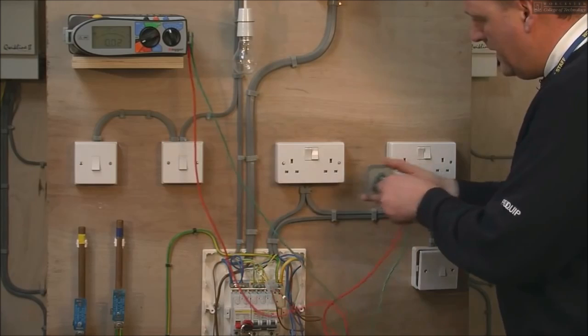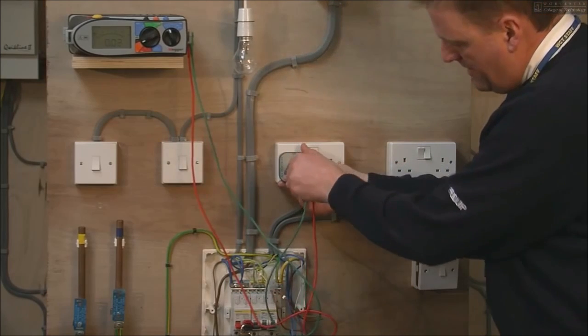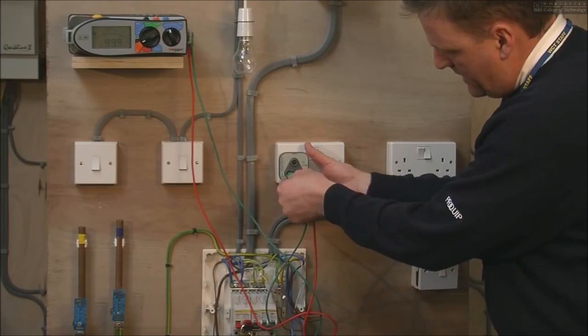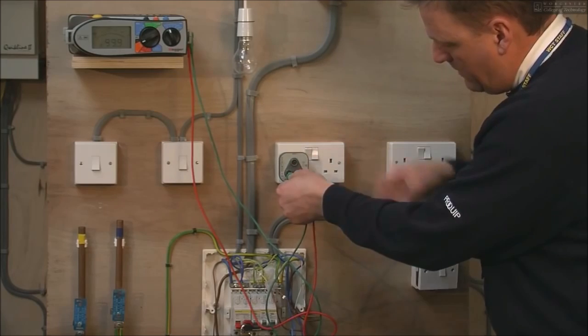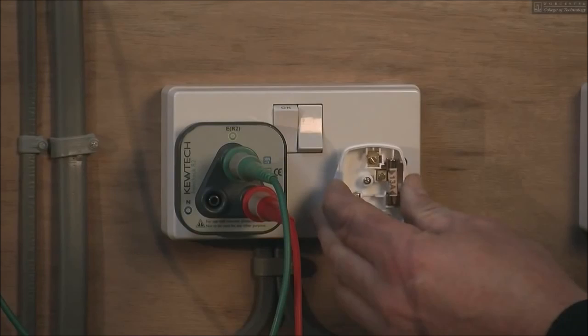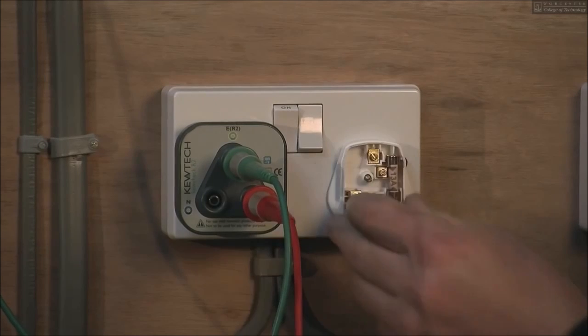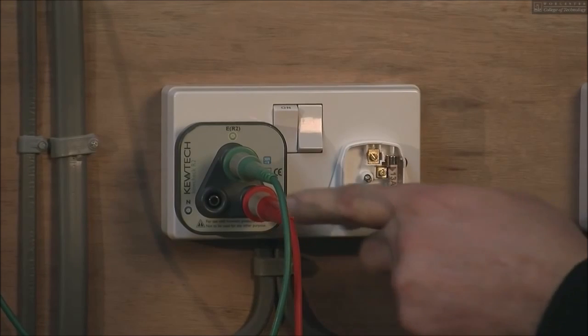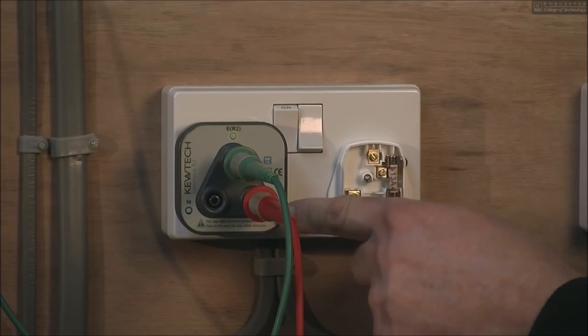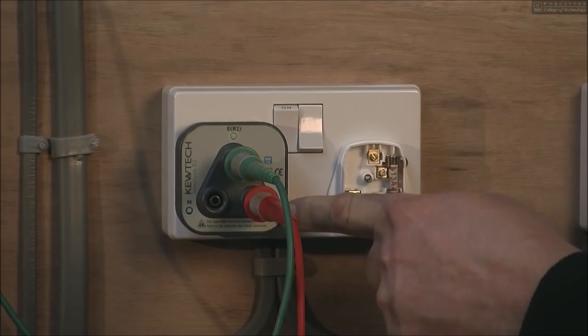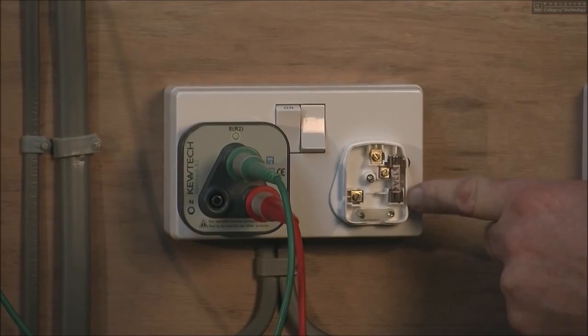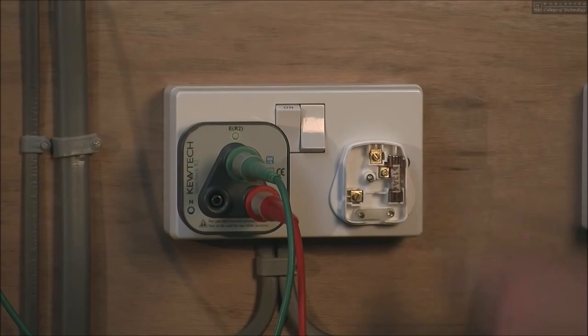Now, when we did the original test, first test, we had a reading between live and neutral. If I insert this open top plug top, you can see more clearly that on both the tests, this lead has remained on the right-hand side of my plug-in tester. As you can see, on the right-hand side of the plug top is the fuse. On both tests, these conductors here, the two brown conductors, have been used in both tests and given us readings.